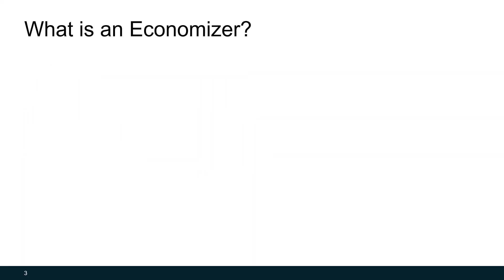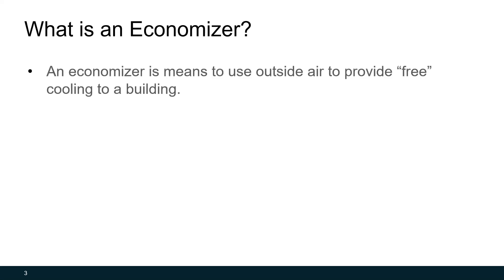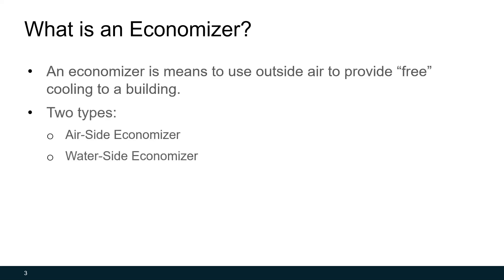So what is an economizer? Imagine you're in a building and it's 55 degrees outside, and our building air conditioning system typically supplies 55 degree air to keep the building cool. Why would we run our air conditioning system to condition air down to 55 degrees when the air outside is already at 55 degrees? What if we just use that outside air to cool the building? We can do that through an economizer — it's simply the means to use outside air to provide free cooling to a building. We can do that with an air side economizer, where we supply the air directly to the building, or a water side economizer, where we use the outside air to cool our chilled water system.